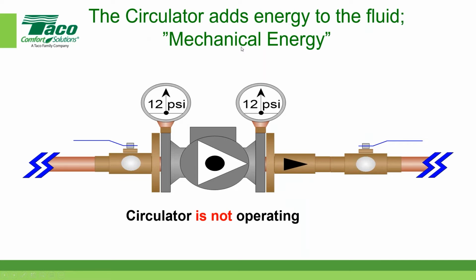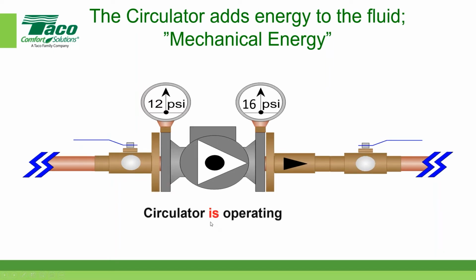Anyway, the circulator adds mechanical energy. Again, you're going to see it in the form of PSI. Notice in this scenario, the circulator is not running. As soon as I turn the pump on, now I can see the evidence of the mechanical energy that the circulator is adding to the fluid. Now it's operating, and I can see that I gained 4 PSI. That's fairly typical of a small little circulator that was sized appropriately.